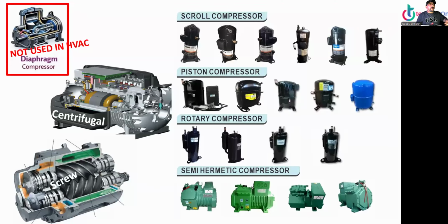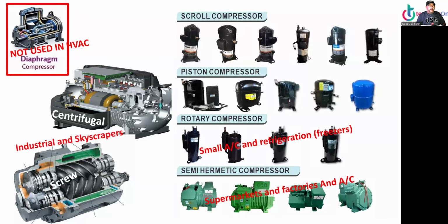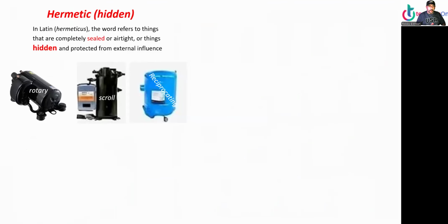And so we have also the diaphragm. It's not really used in HVAC. Alrighty, so the rotary compressors are for small AC, refrigeration, and for freezers. And the hermetic and semi-hermetic compressors are for supermarkets, factories, and big air conditioners. Industrial and skyscrapers use the centrifugal and the screw. And the rest, scroll and pistons, are for residential and commercial AC and refrigeration.